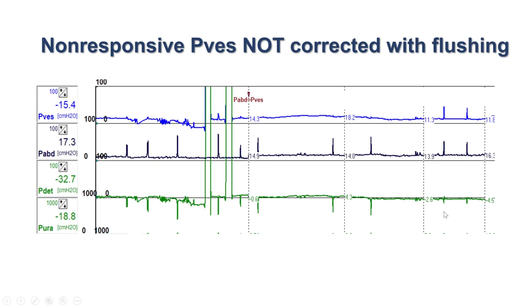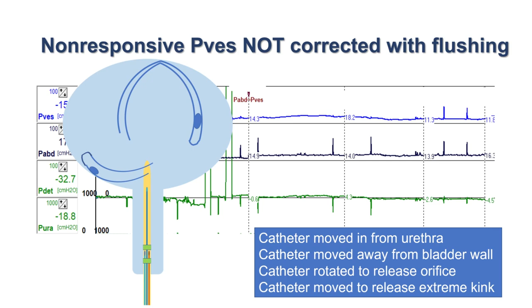Sometimes the P ves, even after flushing, does not respond. Generally, the common causes are that the catheter is kinked in the bladder, or the bladder is so empty that the measurement hole of the P ves is abutting the urethral mucosa. So we move the catheter here and there, rotate it, take it out a bit, and flush the bladder so that it's filled a bit. These are the measures to get the recording again, like in this graph you can see in the later part.